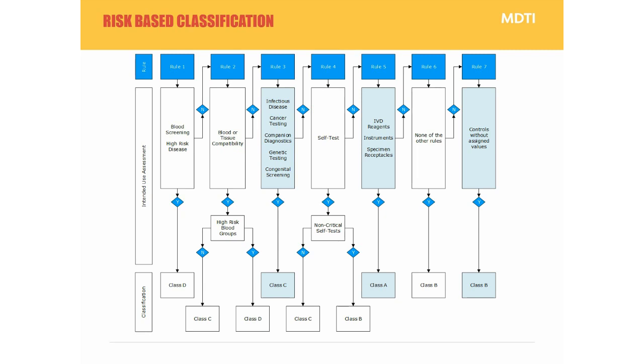There are some routes to the high classification D risk-based designations, and those really come from rules 1 and 2, as you can see there. So if you're blood screening or a high-risk disease diagnostic, you're going to be in class D. Similarly, if you're looking at blood or tissue compatibility issues, you're at least class C, possibly class D as well. Those are a fairly good reflection, especially when you move on to rule 3, of the assays that were covered by the list A and list B products in the current directive.